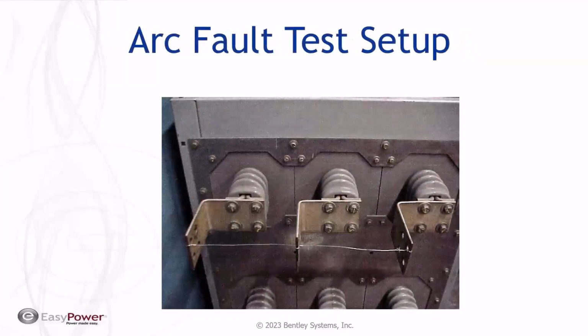Well, in the IEEE battery of data testing that was done, the tests generated an arc by initially having the current flow through a very thin wire, and all that current melted the wire, causing the arc to establish, and that's what permitted them to run the tests to characterize the nature of the arc itself. And it turns out if the arc is established, even a single phase to ground, if the plasma ball is large enough to touch electrified buses, that arc will propagate to other parts of the system.